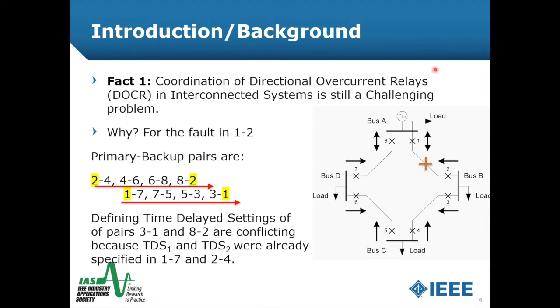Why? For this case, we identified four different buses and we check what happens if we get a fault in between relay one and two. We obtained the primary-backup pairs, starting from the fastest trip to the non-fast trip. The first pairs are 2-4, 4-6, 6-8, and 8-2. From the other side, we got 1-7, 7-5, 5-3, and 3-1. However, defining the time-delayed settings for pairs 3-1 and 8-2 could be a challenge.